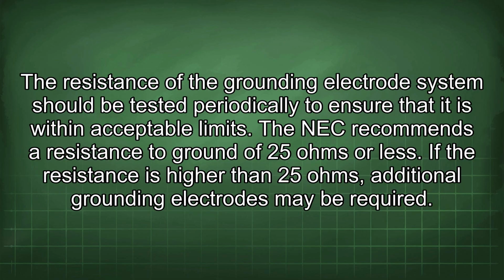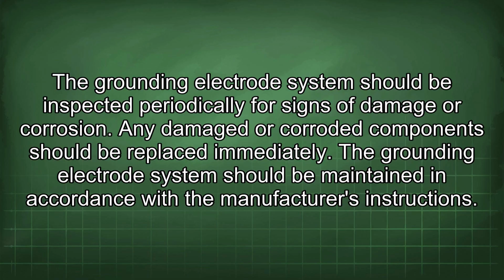The resistance of the grounding electrode system should be tested periodically to ensure that it is within acceptable limits. The NEC recommends a resistance to ground of 25 ohms or less. If the resistance is higher than 25 ohms, additional grounding electrodes may be required. The grounding electrode system should be inspected periodically for signs of damage or corrosion. Any damaged or corroded components should be replaced immediately. The grounding electrode system should be maintained in accordance with the manufacturer's instructions.